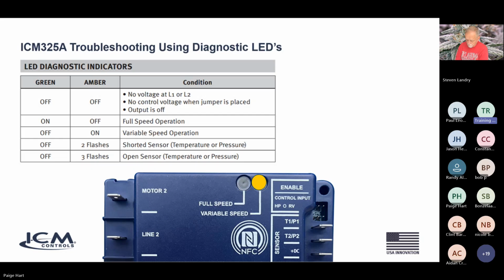And then it will see, okay, where is my pressure? If it says, hey, I need to slow this fan because my pressure is not high enough, then it will slow the speed down and build that pressure up and try to maintain the pressure that you have on your set point within plus or minus 15, 20 psi. So it's going to ramp up and slow down, ramp up and slow down, and try to constantly maintain an even head pressure.